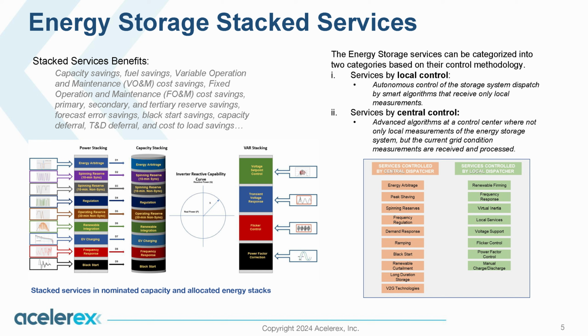With this, storage creates capacity savings, fuel savings, variable operation and maintenance savings, reduces quantities of generators needed. It saves on primary, secondary, and tertiary reserves. For example, without storage, if you wanted to secure a load, you sometimes have to run extra generation, so if one generator fails, the others take over the load - that leads to fuel burn. Whereas if storage is sitting there, it can sit idle and then respond if there's a loss in supply, like loss of grid or loss of a generator.